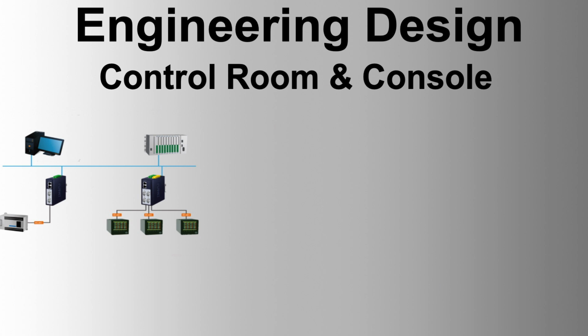Noise. Maximum noise levels in control room areas are specified for different zones, with control rooms having a preferred maximum of 40 dBA. Noise sources that could disturb voice communication, such as the cooling fan noise of VDUs and acoustic alarms, should be controlled. Measures for controlling airborne and contact sound transmission should be considered since control buildings are located near plants.